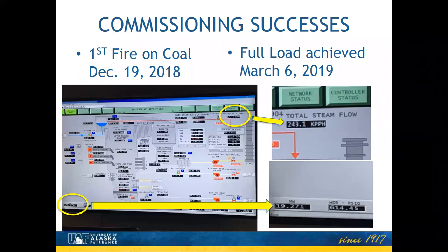Yeah, we do have a commissioning subcontractor who's providing the current plant operators, and they wrote the standard operating procedures based on what the boiler manufacturer, turbine manufacturer, and condenser manufacturer recommended. And then the university's operators have been cross-training into that new plant for quite some time now. And there's one of their operators at the current facility that's always in the new one operating it.